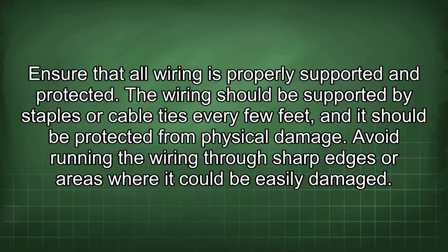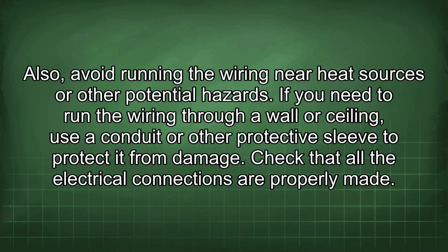Ensure that all wiring is properly supported and protected. The wiring should be supported by staples or cable ties every few feet, and it should be protected from physical damage. Avoid running the wiring through sharp edges or areas where it could be easily damaged. Also, avoid running the wiring near heat sources or other potential hazards. If you need to run the wiring through a wall or ceiling, use a conduit or other protective sleeve to protect it from damage. Check that all the electrical connections are properly made.